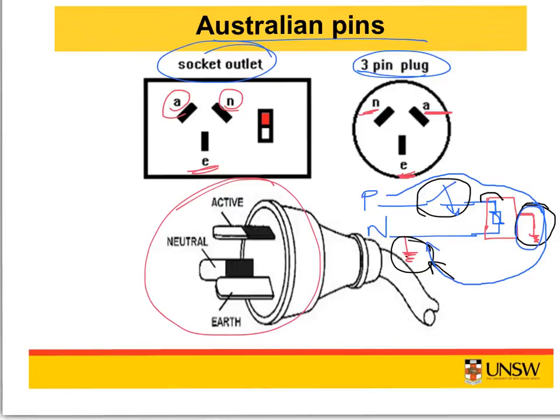So therefore, since the resistance of the grounding wire is very low, excessive current flows through the circuit breaker, and the circuit breaker trips because of the very high current flowing through it. And therefore, the 3-wire system operates in a manner which transforms a safety hazard into an overcurrent condition, causing the safety hazard to be automatically cleared by the circuit breaker. The circuit breaker is used, therefore, as both an overcurrent protector and a shock hazard protector.